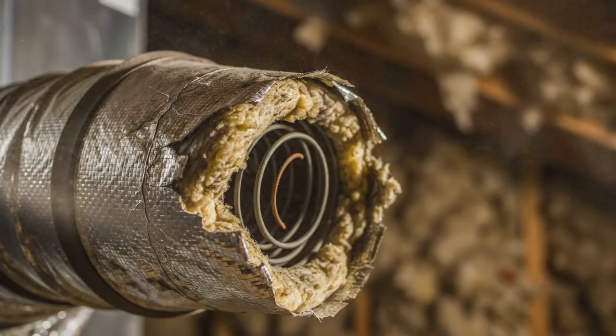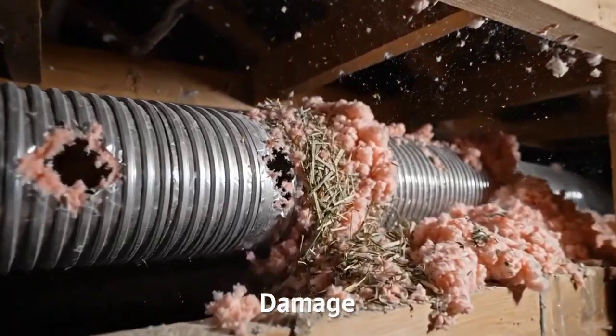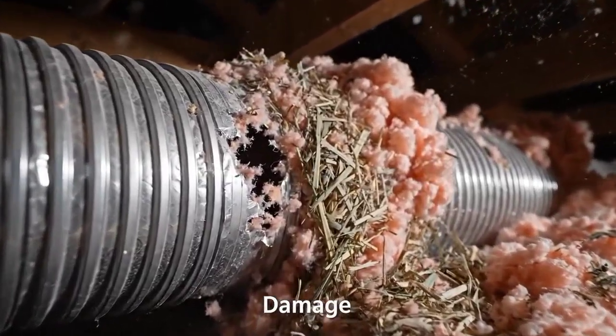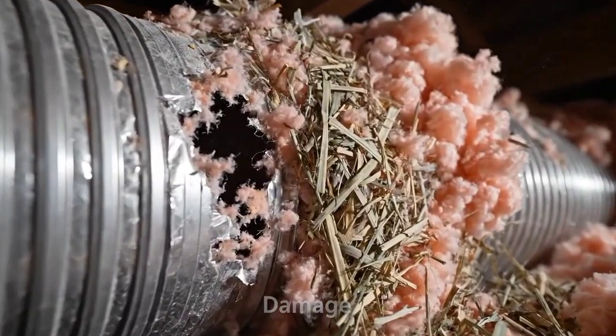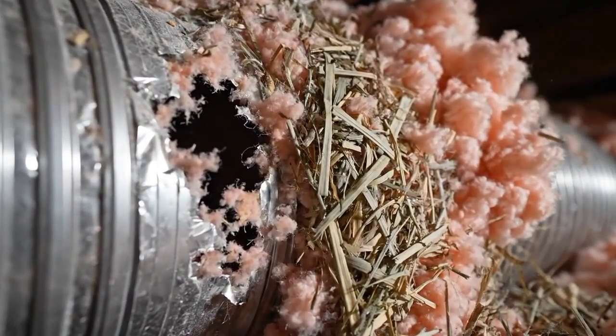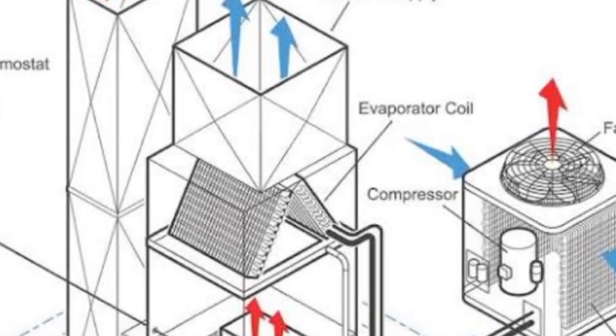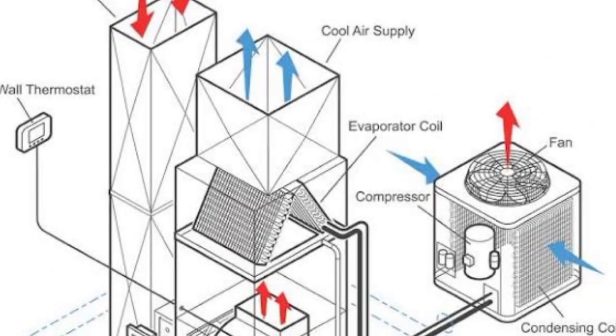The National Comfort Institute went out and tested hundreds of residential systems in the field. What they found was brutal. The average home was only getting about 57% of its rated airflow. That means if you bought a 3-ton system, you're getting the performance of maybe 1.5 tons.